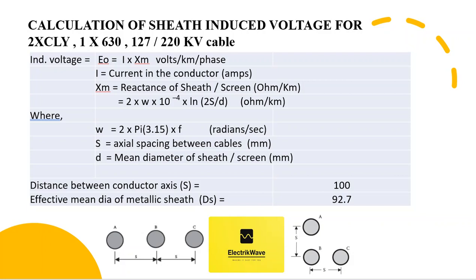Now we will calculate sheath-induced voltage for a single-core 630 square mm, 127/220 kV cable. The induced voltage depends on the current in the conductor and the reactance of the sheath or screen. W is dependent on system frequency, S is the distance between conductors, and DS is the effective mean diameter of the metallic sheath.